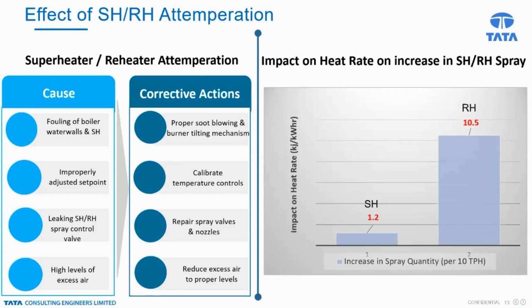To give a perspective, consider what happens for every 10 tons of spray water quantity increase. For the superheater, the impact on the heat rate is not so much, but even 1 to 1.2 kilojoule per kilowatt hour is the impact for a typical 800 megawatt power plant. In the case of the reheater circuit, the impact is huge: 10 kilojoule per kilowatt hour for every 10 tons per hour increase in the spray water quantity. So we should take all measures to ensure that we have optimum, or as minimum as possible, spray water for both superheater and reheater.